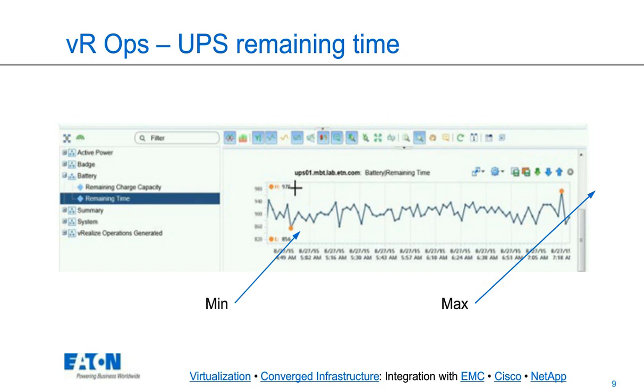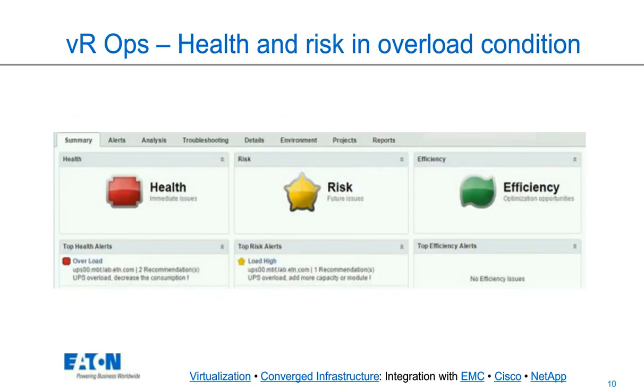The last thing I want to show you is that if there is a problem with the UPS, it's going to change the badge color of the health and the risk part. What we're showing here is we forced the UPS to go near 100% of its capacity, and that drove the health badge to a red color, and it gives you an alert underneath that calls it the overload.